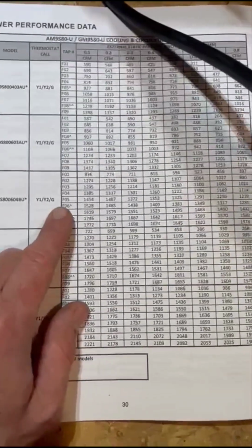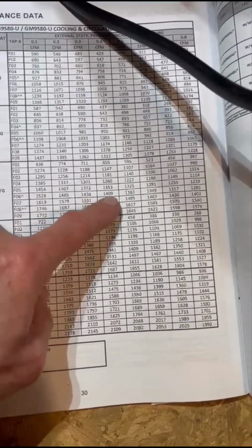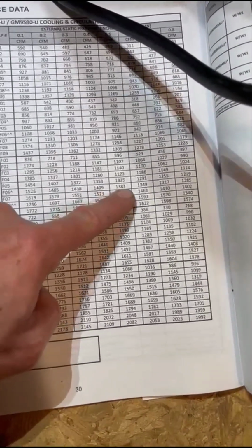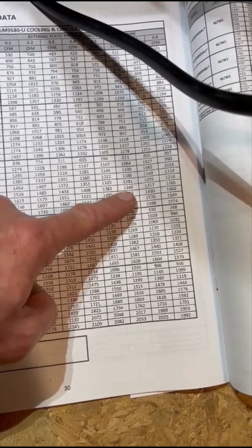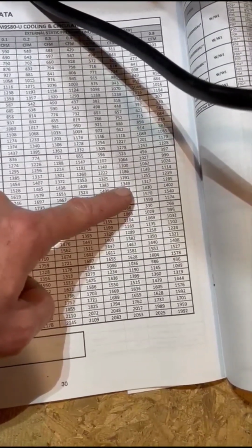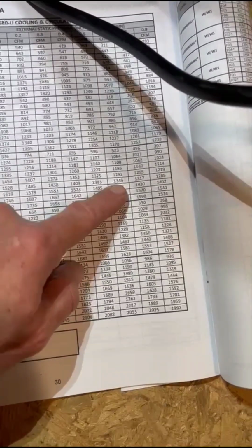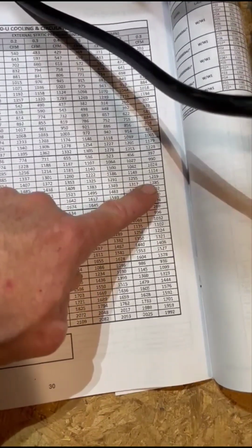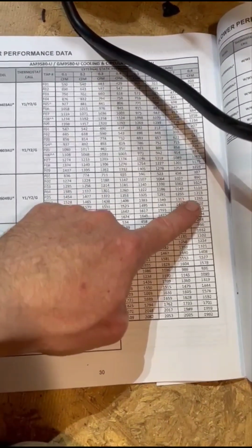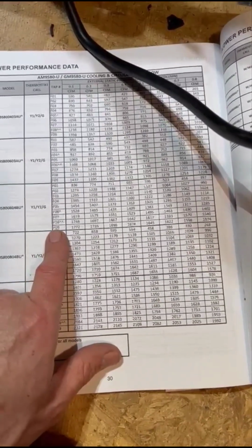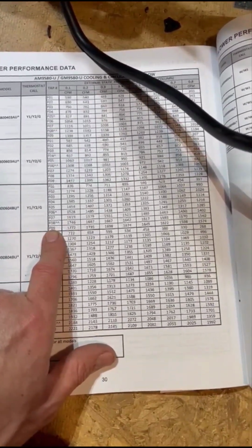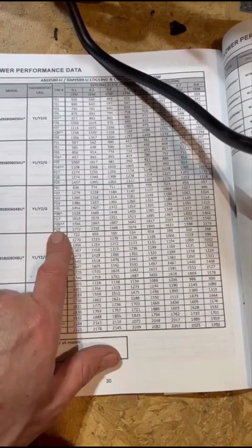Now, since we did the airflow class, we know that most of these units gonna run around 0.6 to 0.8. So if we're gonna put it on 0.6, it should be around 3.5 ton capacity. If we're gonna put it on 0.8, it's gonna be 3 ton capacity. So we're gonna check the static pressure right now. On high speed, I'm gonna select tap 9, and then according to that, it will determine which tap I'm going to select.